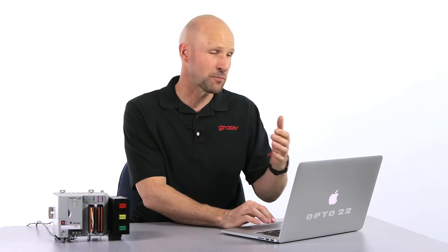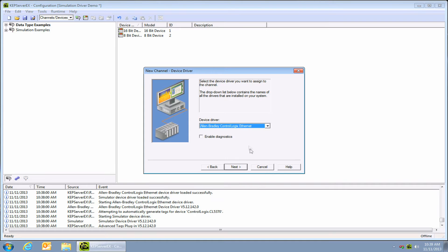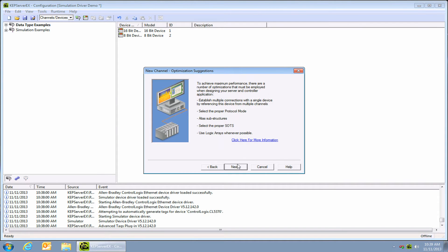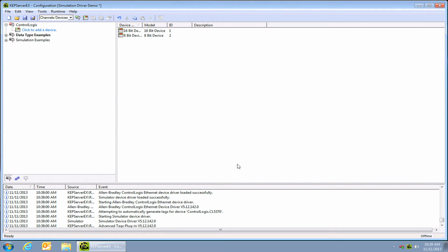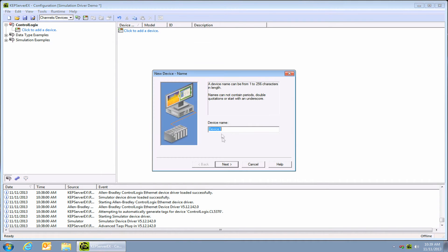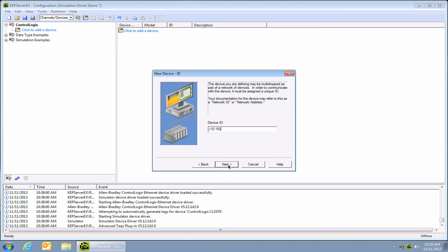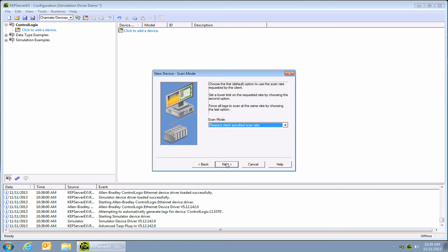Okay, I got a little excited there, but let's get back to work. Click on next, and if you have more than one network interface card, be sure and select the one that the AB controller is on. Go ahead and select the defaults for all the remaining dialogues. Now that the channel is created, let's add a device. Click on add device and give it a name — I'm going to call it CL5370 for my PLC. Select the device; the ID is the IP address.